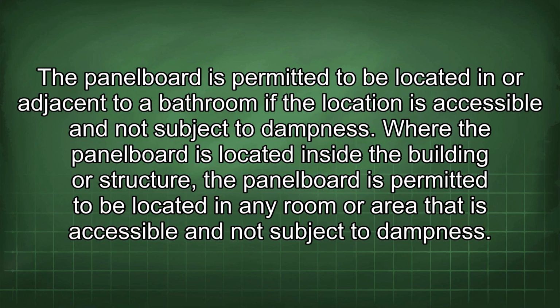The panel board is permitted to be located in or adjacent to a bathroom if the location is accessible and not subject to dampness. Where the panel board is located inside the building or structure, the panel board is permitted to be located in any room or area that is accessible and not subject to dampness.